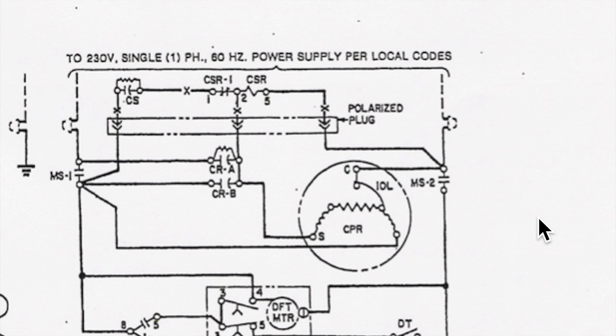So let's look at how this is wired up. I'm going to start over here to the common. That's upstream of the main contactor, right there, goes to common through the start winding over to these two capacitors. This is kind of interesting because one of these capacitors is downstream of the contactor, and one of them is upstream. These are run caps. The total of these two equals the run cap size or strength. And if I go back the other way and follow the power from here, with the unit off, the power is going to go through here, through this capacitor, and you notice there's a resistor in that capacitor. But then the power is going to go through here. It's not coming from this one because this one's downstream of the contactor and goes over to the start winding.